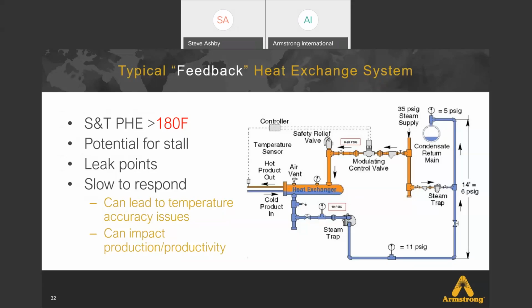But probably just as important, if not more, is that the temperatures swing based on high demand and then low demand. It takes a while for the modulating control valve, the temperature sensor, and the controller to communicate with each other and finally get to a set temperature. It takes time, and it can be quite an issue as far as productivity. So again, this is what we call a feedback system.